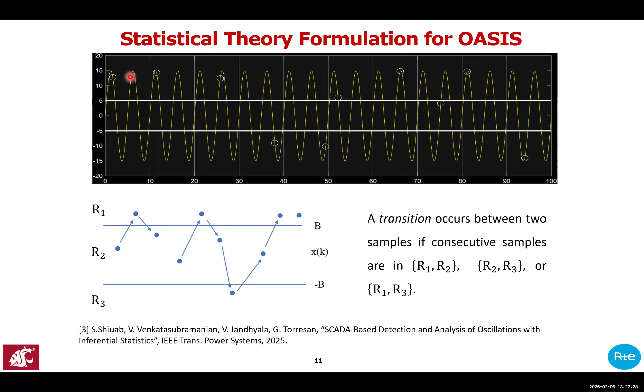So how do we know this 5 is an acceptable number for counting this to be an oscillation event? Because we may have some noise related spike which pushes the signal outside, and we don't want that kind of false alarm or false detection. And so this is where we need the statistical theory. Here I'm just illustrating how this concept works. We have taken 3 different waveforms with 3 different amplitudes, and I have fixed the band at plus minus 5 megawatt. In the first one, the amplitude is 4, so all of the observations are within the band, there is no transition. So this would be the rejection that there is no oscillation event, at least event of interest, according to what we have specified as the threshold.